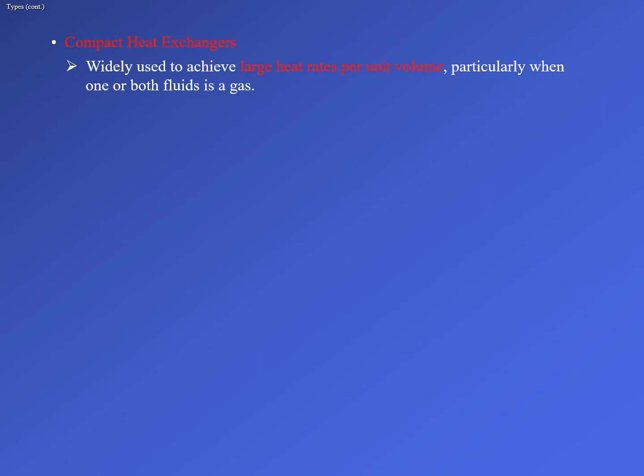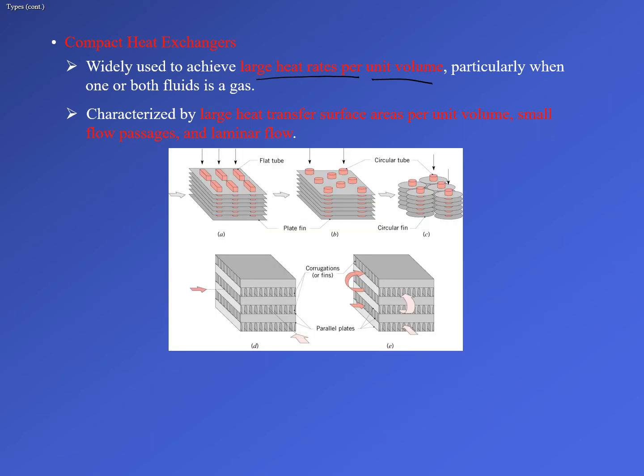Compact heat exchangers are designed to achieve a large rate of heat transfer per unit volume. They use many passes, lots of tubes, and fins — flat, circular, or corrugated — to maximize interaction between the two fluids across the minimum possible volume. Corrugated fins are typically used when air rather than liquid is the cross flow fluid.